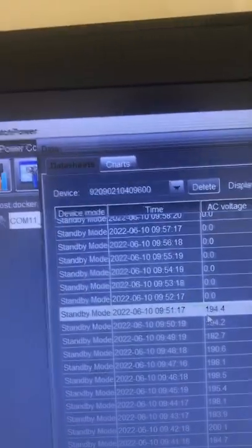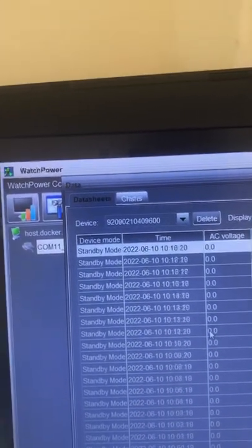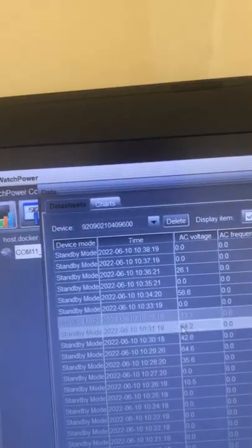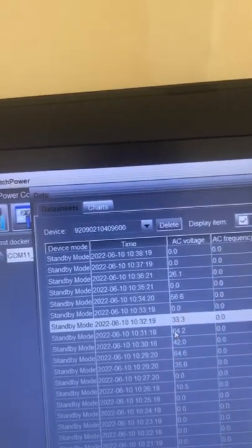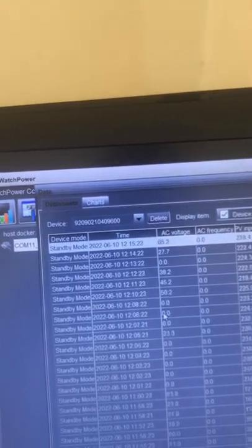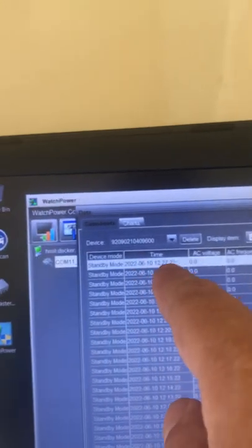If I look at the data for the same day, let me scroll down to 9:50. So you see that at 9:51 the voltage becomes zero. It stayed zero. Then the power was restored at about 10:26. But the voltage never grew to more than about 50 volts, and the unit failed to detect that AC power was restored. And until now, it's 12:27, the last point.